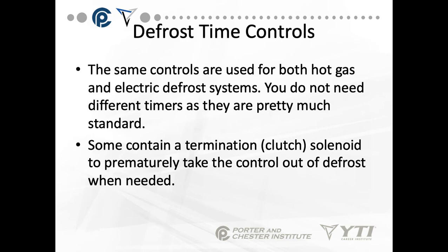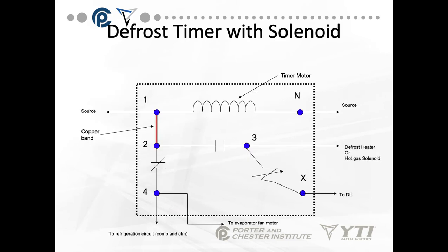Here we have a diagram of a defrost timer with a solenoid. These pins are numbered, and by looking at the time clock you can see where the numbers go. There's always a diagram that comes along with the time clock, usually on the inside of the door. Source voltage comes to pin 1. There's a copper band that connects pin 1 and 2. If you have different voltages — like low voltage on solenoid devices — you can use different voltage levels by removing this copper band and putting other sources. Between 1 and N we have our motor; source goes on 1 and comes out on N.